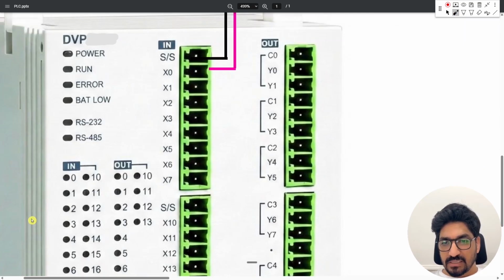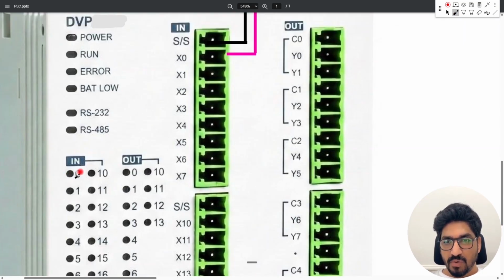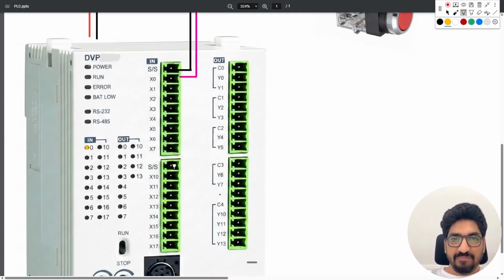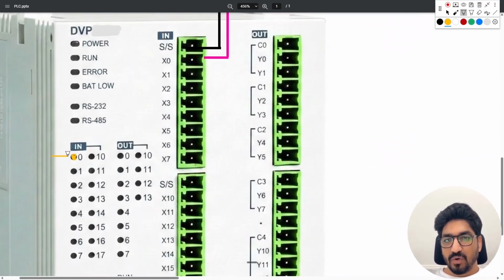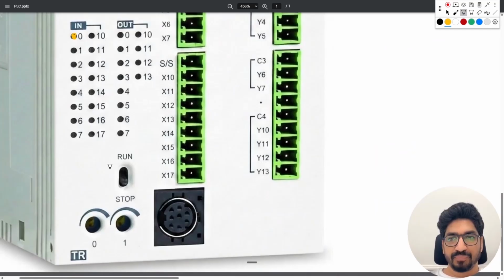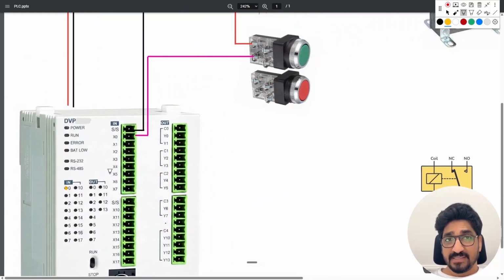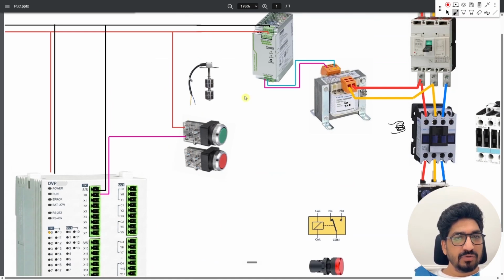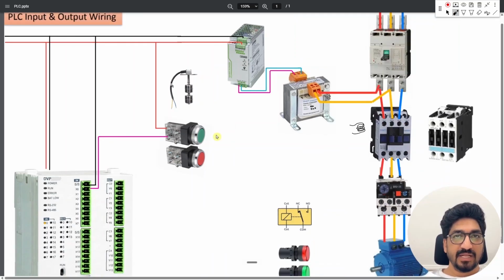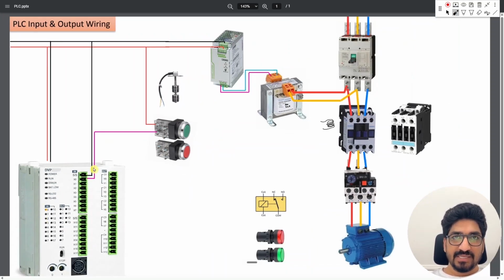X0 triggered means this input 0 will be glowing, it will glow basically. This becomes live. So this is also troubleshooting - that means if you press the start button and this doesn't glow here, that means there's some problem in the wiring, or the PLC itself. Mostly it's a physical issue - either the wiring is cut somewhere, or this switch is faulty. So that's also a troubleshooting step. But now you understand how the inputs are wired to the PLC.